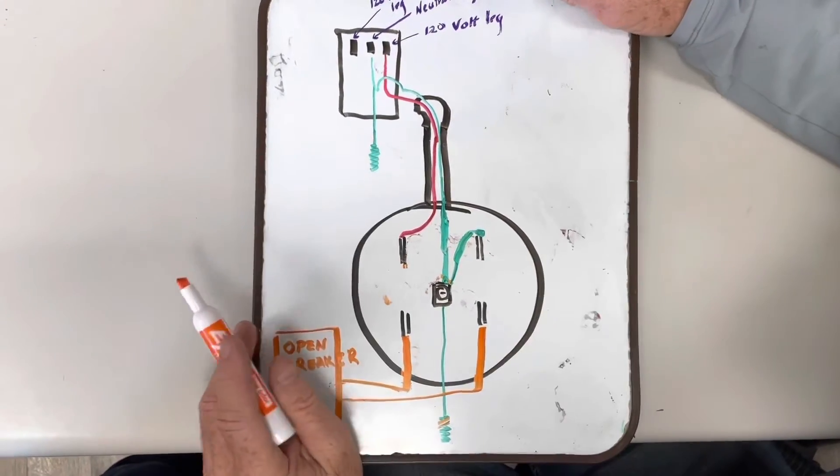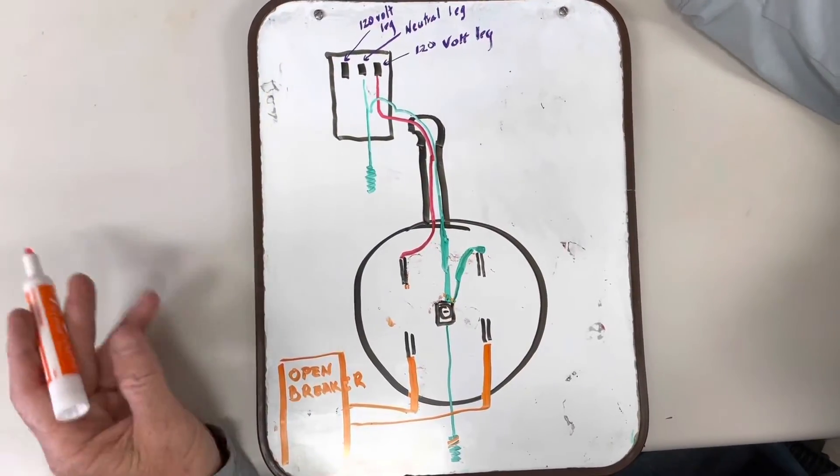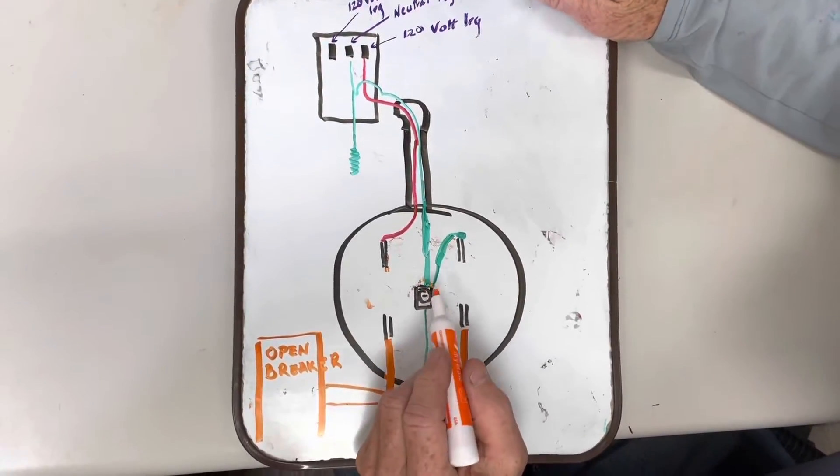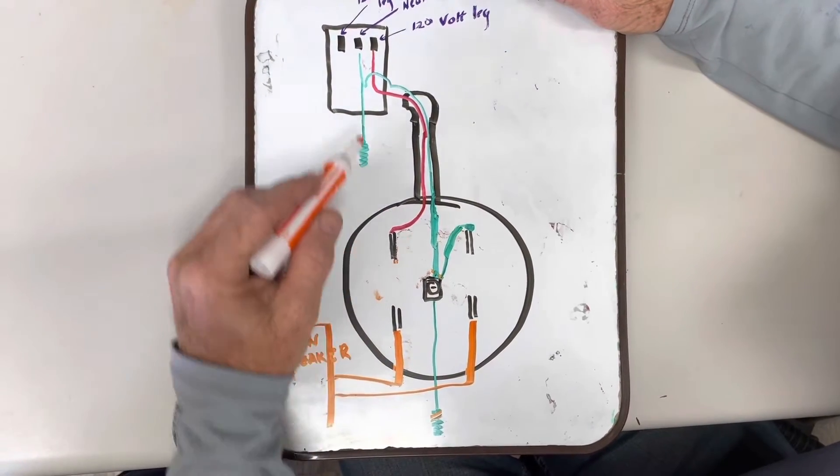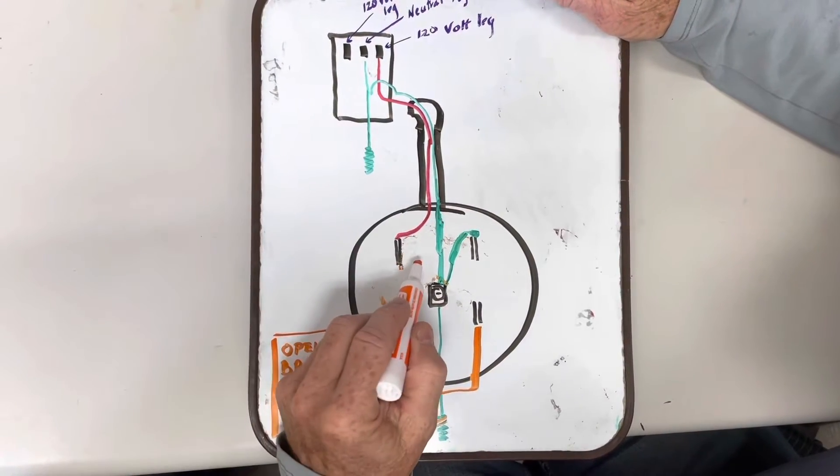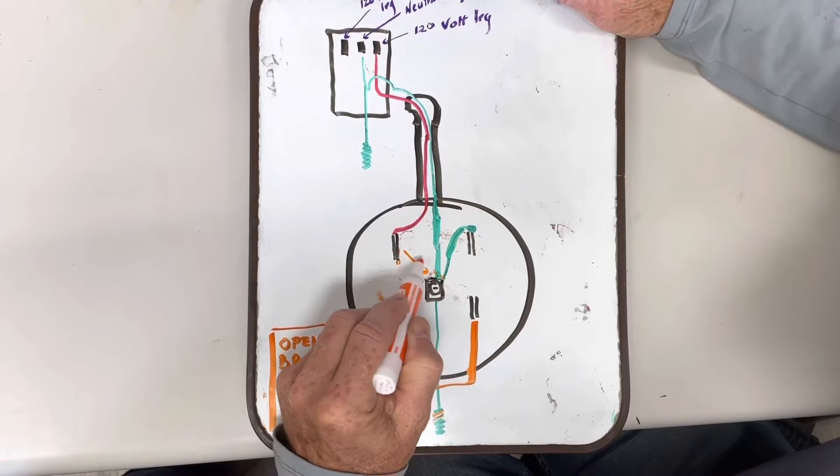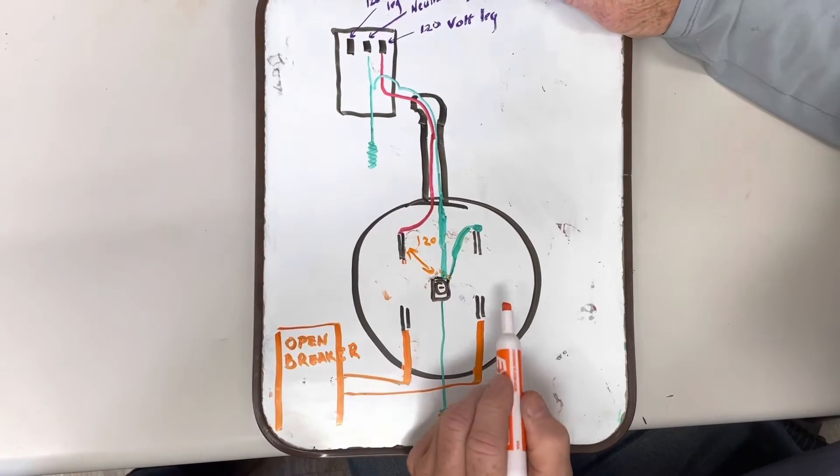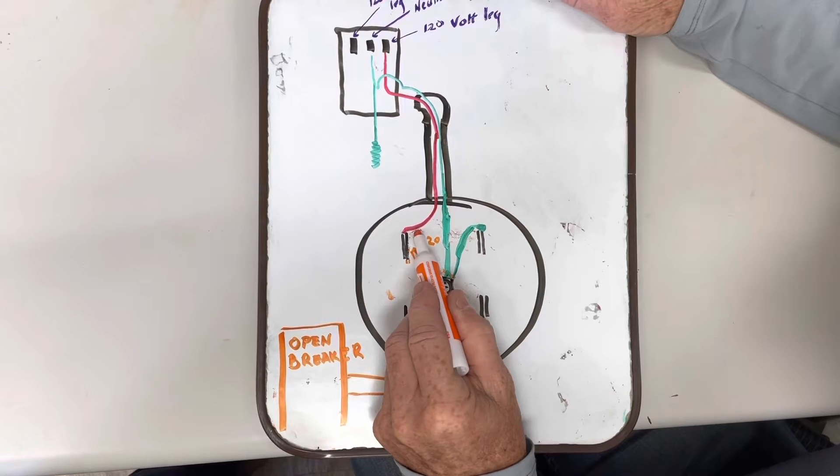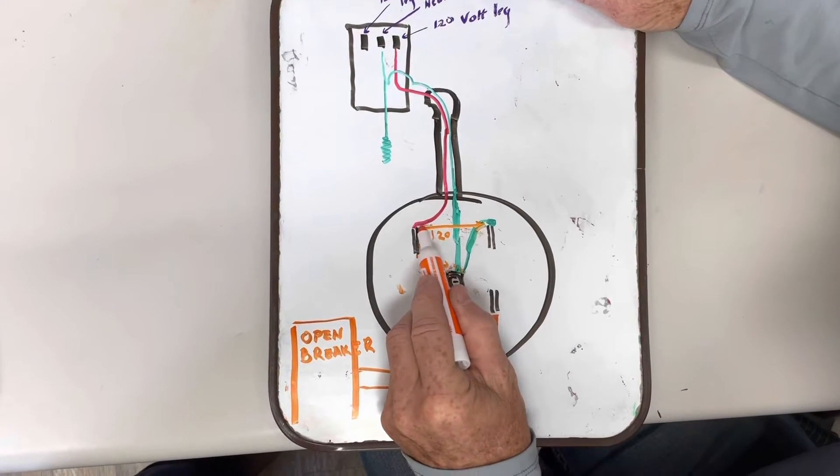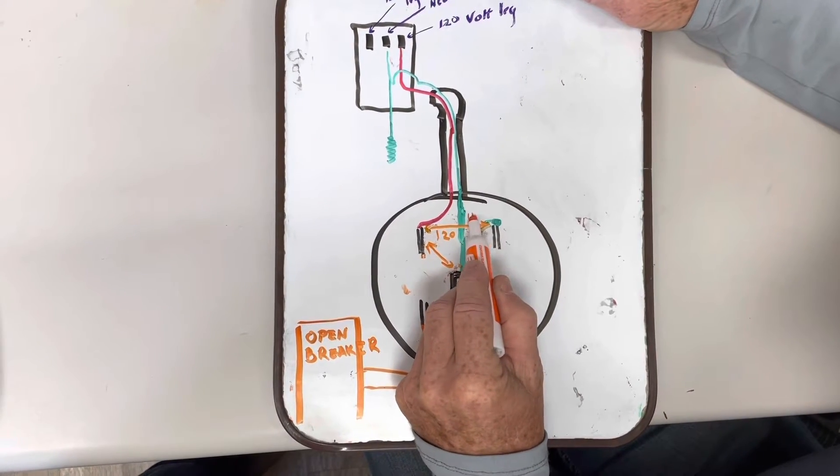So now the next check we're going to do when you come up on it is check your voltages. With the transformer energized, we're going to go from this lug to neutral and we're going to get 120 volts. We're going to go from this leg to this leg with the volt meter and we're going to get 120 volts.